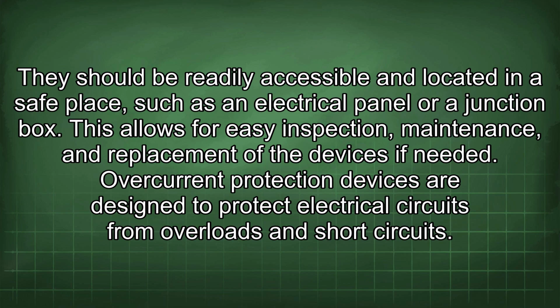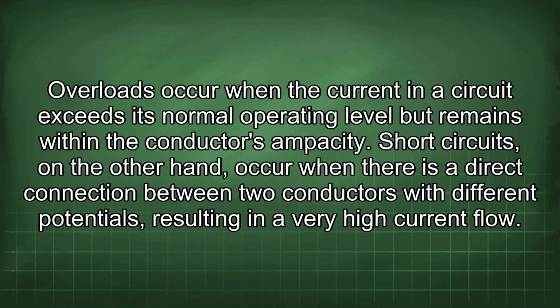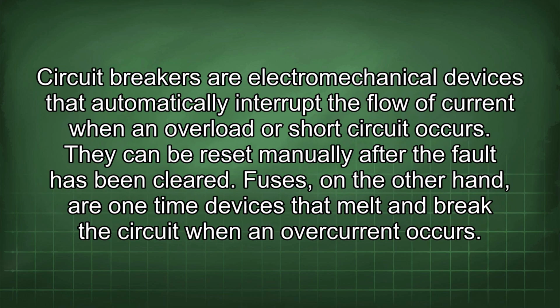Overcurrent protection devices are designed to protect electrical circuits from overloads and short circuits. Overloads occur when the current in a circuit exceeds its normal operating level but remains within the conductor's ampacity. Short circuits, on the other hand, occur when there is a direct connection between two conductors with different potentials, resulting in a very high current flow. Circuit breakers are electromechanical devices that automatically interrupt the flow of current when an overload or short circuit occurs. They can be reset manually after the fault has been cleared.